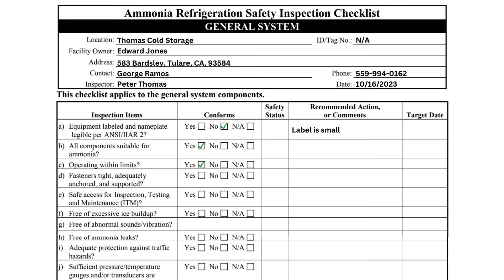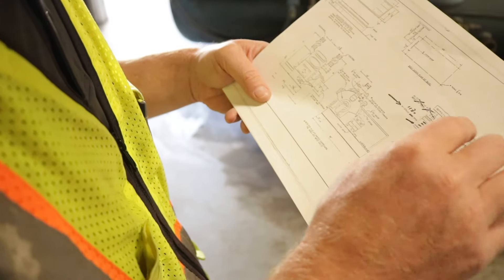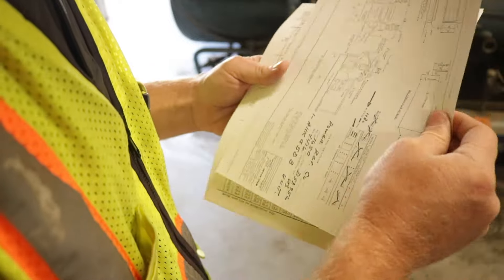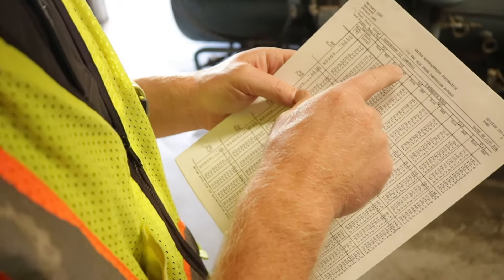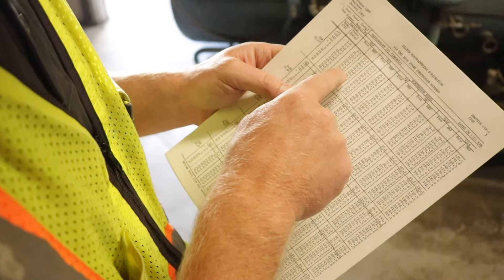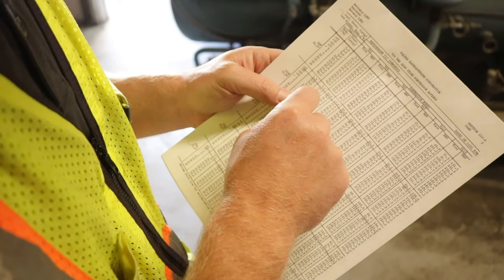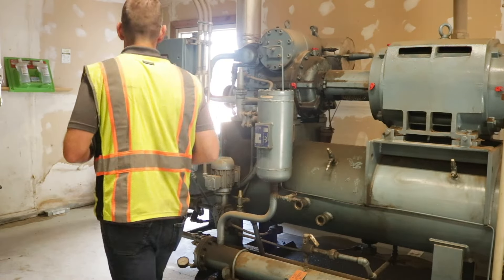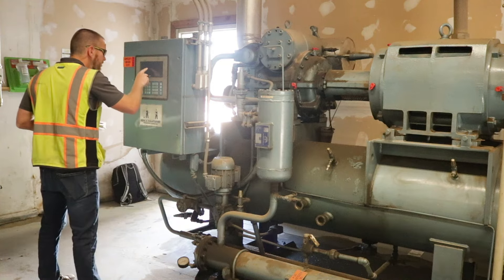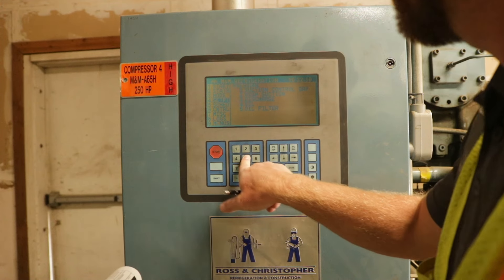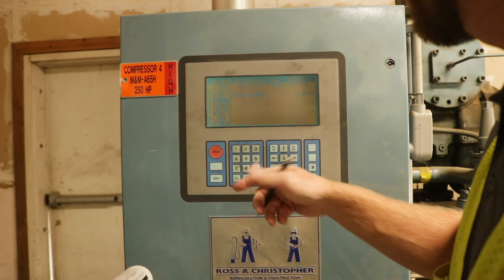Items B and C ask if the equipment in the system is suitable for ammonia and operating within limits. Suitability for ammonia can be verified by the equipment specifications provided by the manufacturer. There are many operating limits that should be observed. Some of the more noteworthy operating limits for a compressor are suction pressure, discharge pressure, oil pressure, and oil level. The pressures can be monitored from analog gauges or microprocessors.